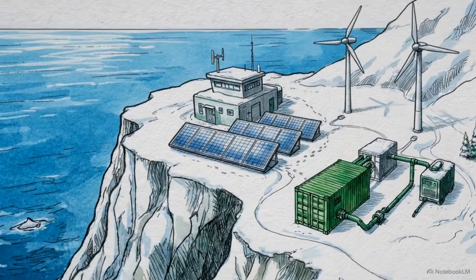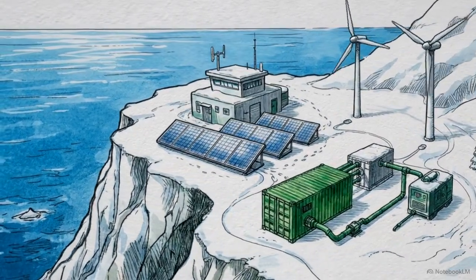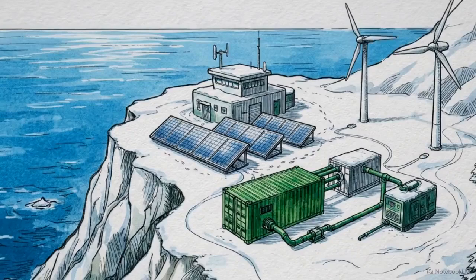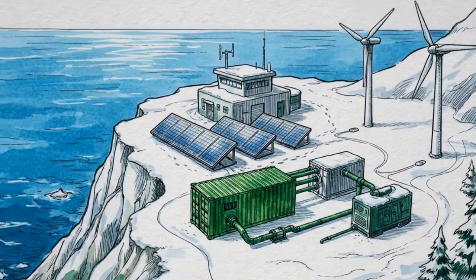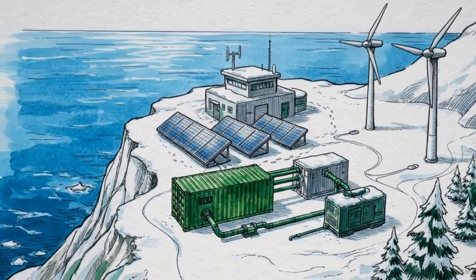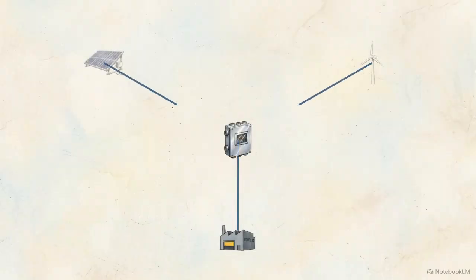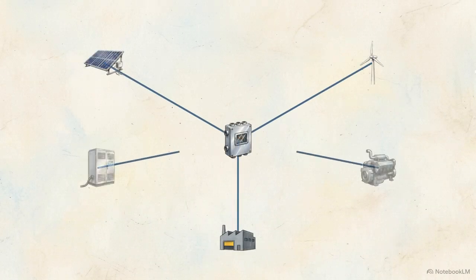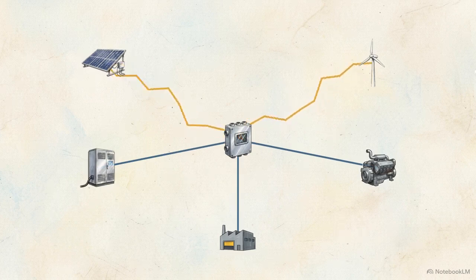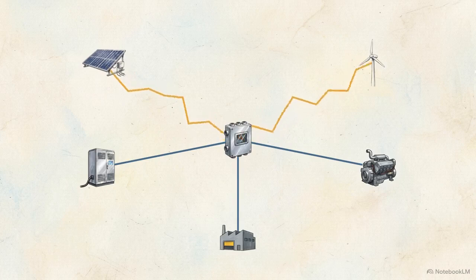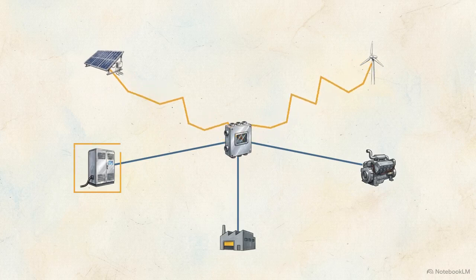An isolated community completely disconnected from the main power grid faces a unique survival test. Every watt of electricity consumed has to be generated locally. A hybrid microgrid relies on solar photovoltaics, wind turbines, a battery energy storage system, and a diesel generator. Their power output is stochastic, spiking and dropping dramatically. The battery has strict physical limits, facing severe charge and discharge bottlenecks, known as C-rate limits.